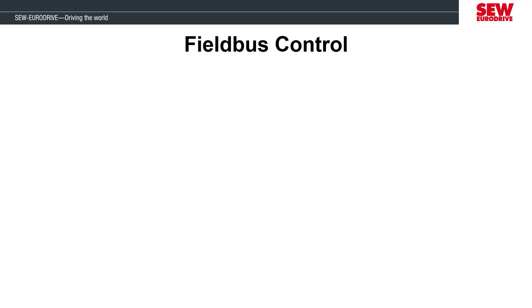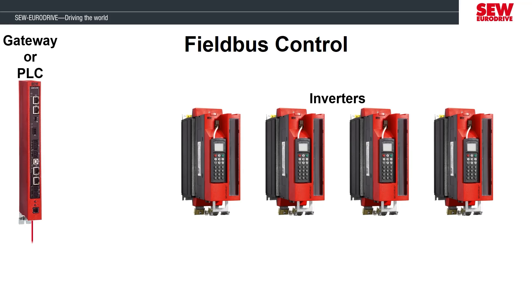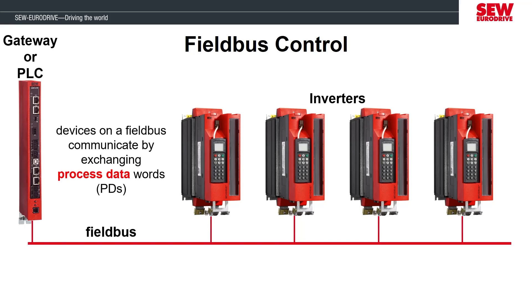If you're unfamiliar with fieldbus controls, you may need a short introduction to a common way it's used. A lot of fieldbus networks will have a gateway or PLC as the upstream device and then one or more inverters as the downstream devices. These will be connected together over an industrial network and will communicate using what's called process data words.